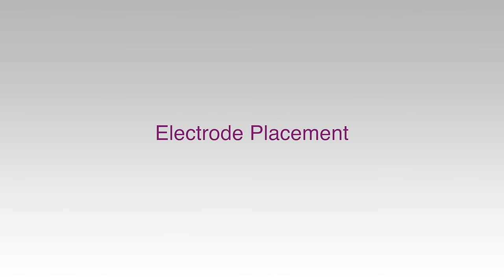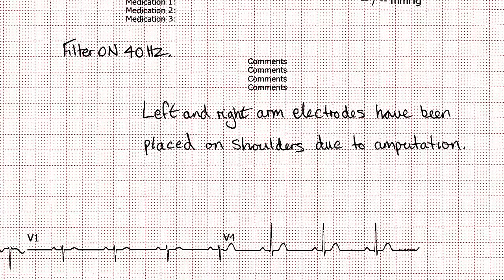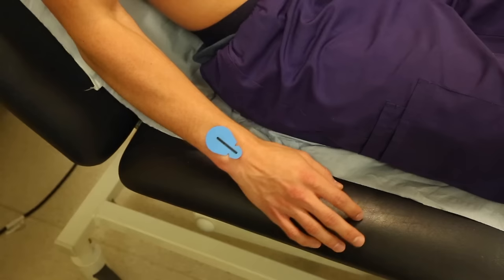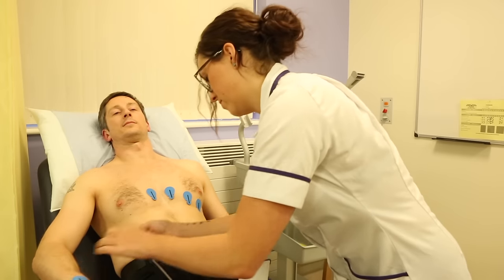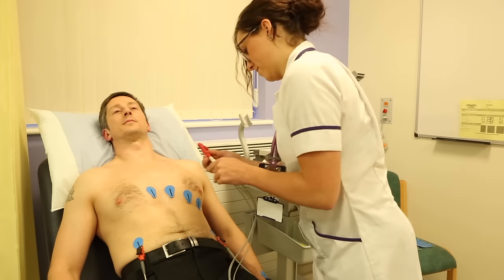Electrodes must be positioned in accordance with the AHA recommendations. If any electrodes need to be sited in non-standard positions, the recording must be labelled with this information to avoid misinterpretation of any altered ECG waveforms. Limb electrodes should be placed on the wrists and ankles whenever possible. Moving the electrodes up the limbs may alter the appearance of the ECG and should be avoided unless there is a significant tremor of a limb or it has been amputated. Limb electrodes must not be placed on the torso, since this causes significant alteration to the wave amplitudes and can invalidate the recording for many diagnostic purposes.